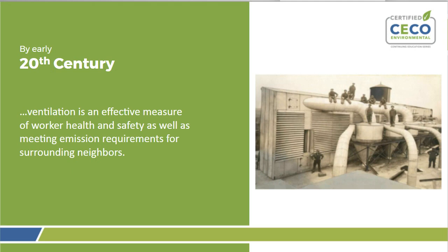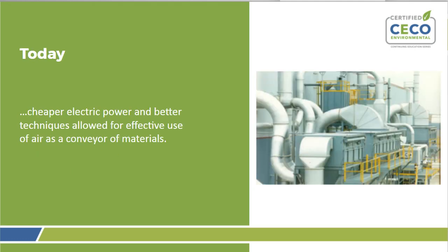But again, with industrial ventilation systems, and especially woodworking, make sure you keep the plant clean. Those guys will be knee deep in dust if you don't have a collection system to protect the workers from breathing the dust, and also to protect the environment and the neighborhood from any dust that could pass through the collection device. Today, if we're talking just collectors here, you can get them in cartridge or bag, wide or tall, usually depending upon the real estate available to put the collection device. With all the technology, you can get them with explosion venting, and choose rotary airlocks or screw conveyors, depending upon how you need to get rid of the material you're collecting. And energy savings comes into play, of course.